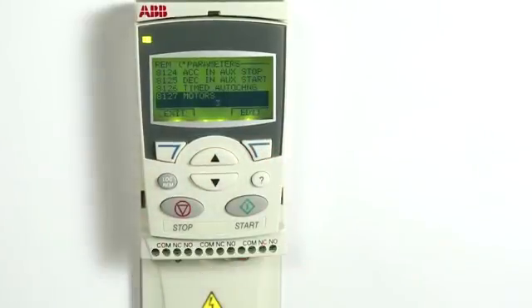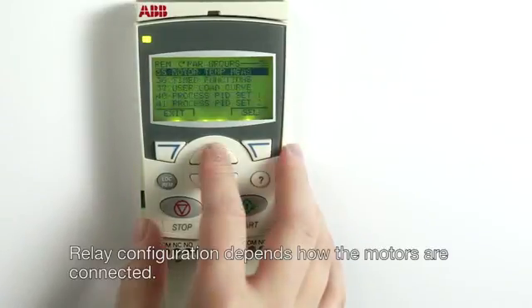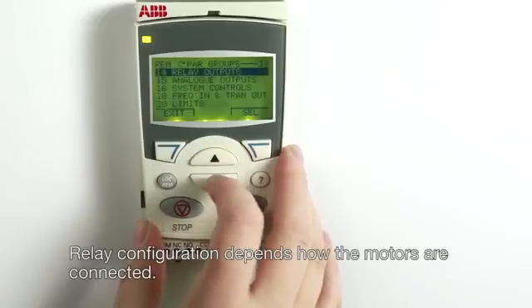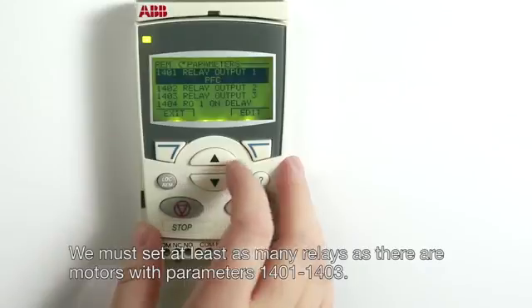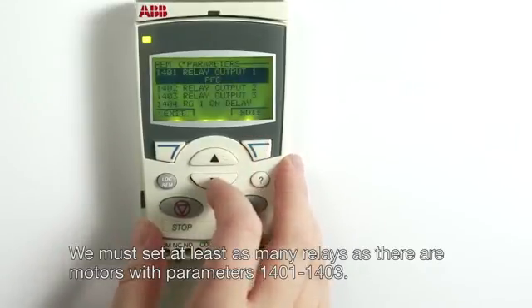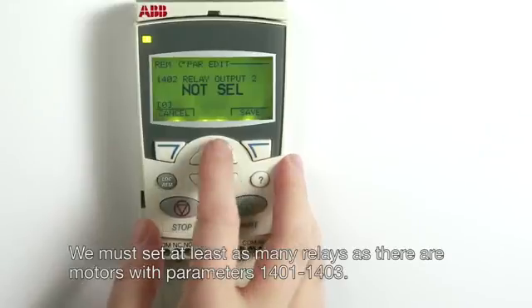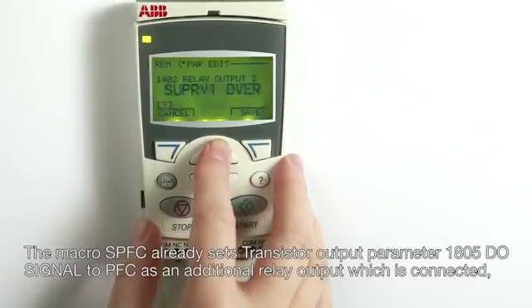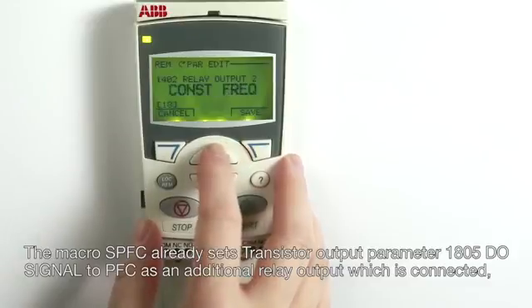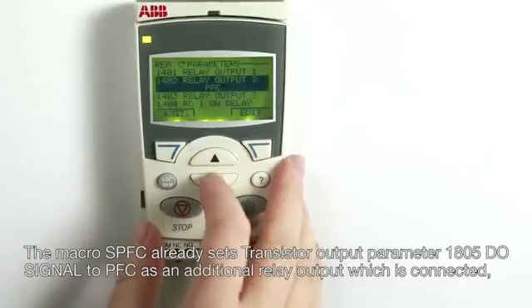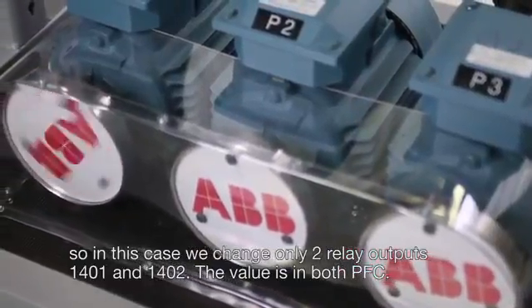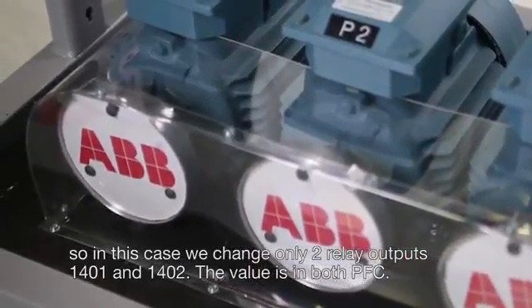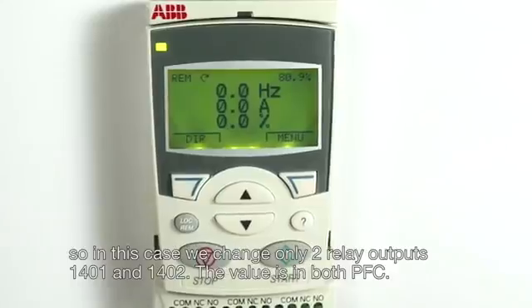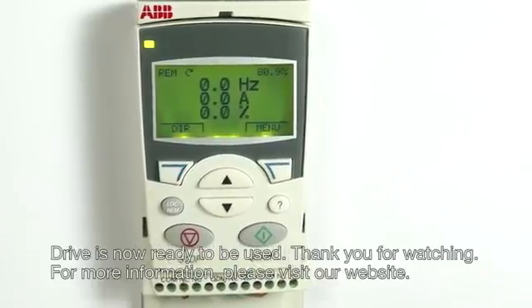Then press Exit. Then go to group 14 Relay Outputs. Relay configuration depends on how the motors are connected. We must set at least as many relays as there are motors with parameters 1401 to 1403. The macro SPFC already sets transistor output parameter 1805 DO signal to PFC as an additional relay output which is connected. So in this case, we change only two relay outputs, 1401 and 1402. The value is in both PFC. The drive is now ready to be used.